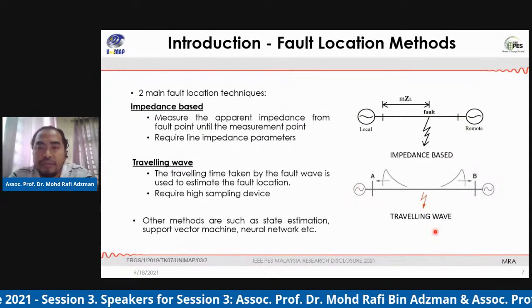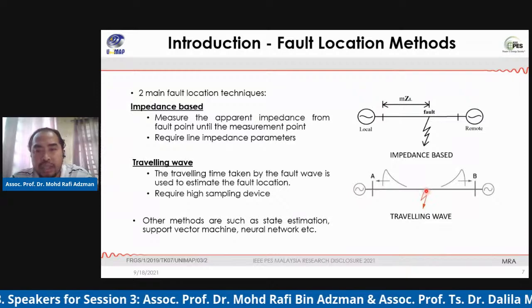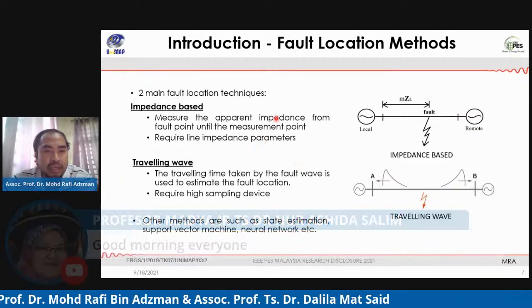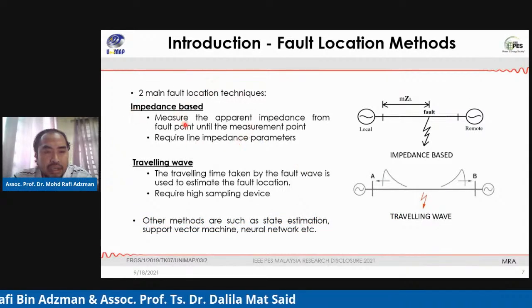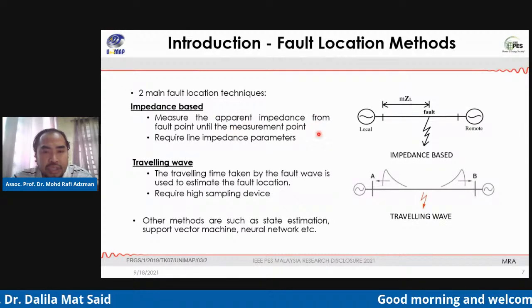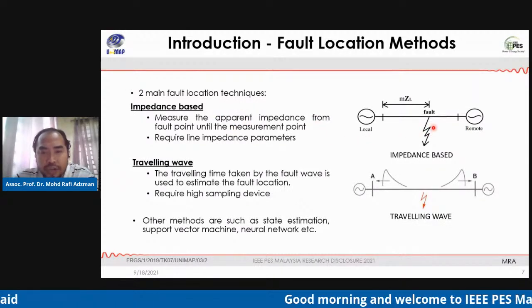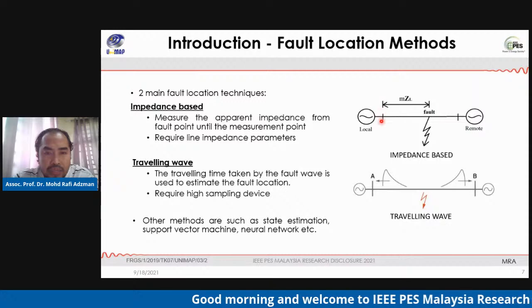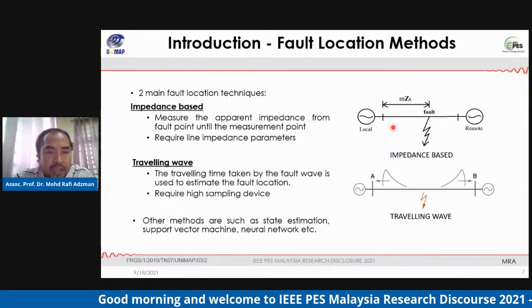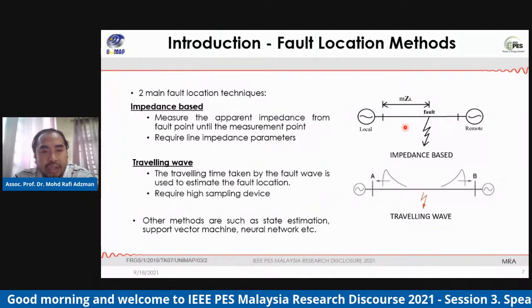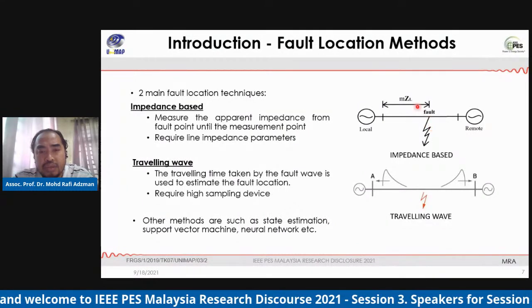And regarding fault location techniques, we can say there are two main techniques that have been used in power system networks. Number one is the impedance-based method. It measures the apparent impedance from the fault point to the local measurement point, and we require the line impedance parameters in order to run this algorithm.